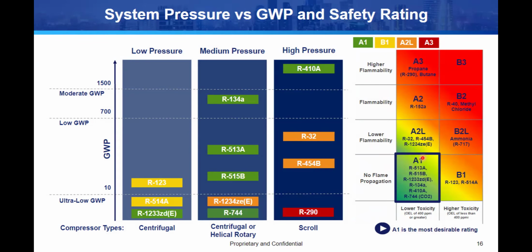So the A1 refrigerants, they're all gone. Every single one of them, with the exception of CO2, has too high of a global warming potential for us to utilize anymore, right? It's not allowed. CO2 is allowed, but that's a whole other set of problems we have in terms of temperature and stuff like that. So no one's using CO2 in the United States for HVAC. So there's no A1s available to us. So we have to go up into the A2 bucket, which means we have to go flammable.